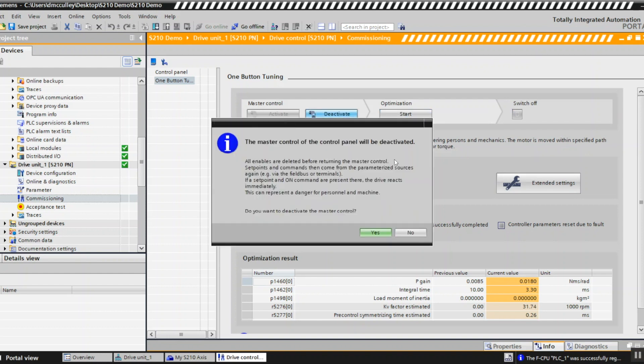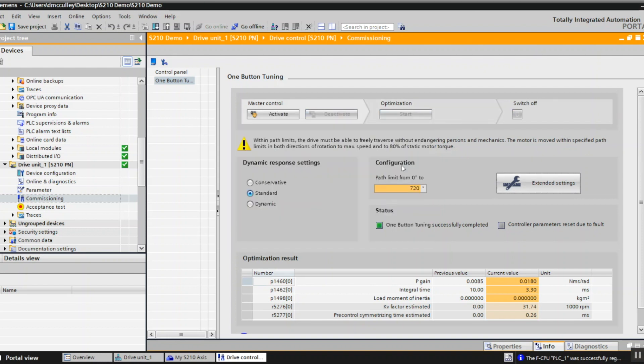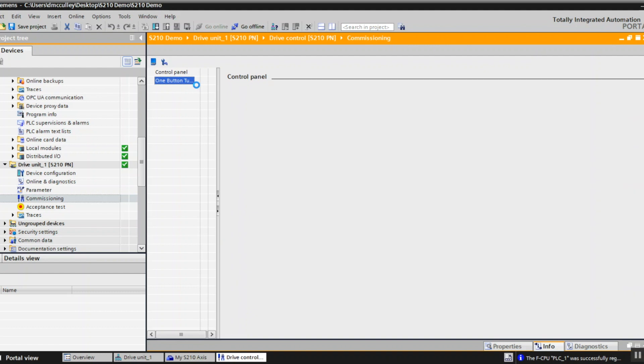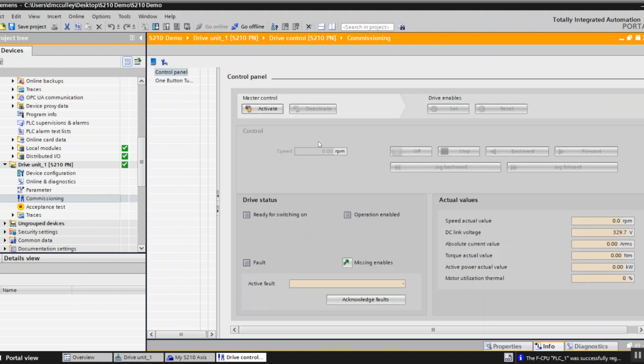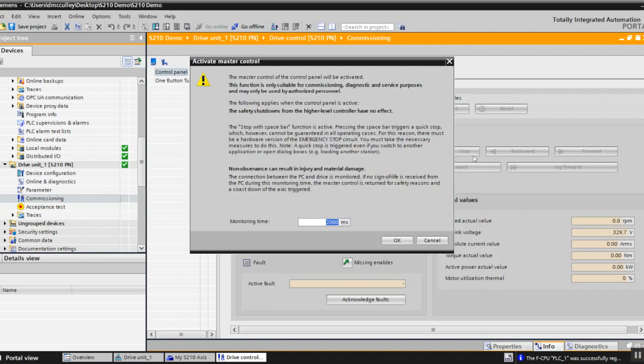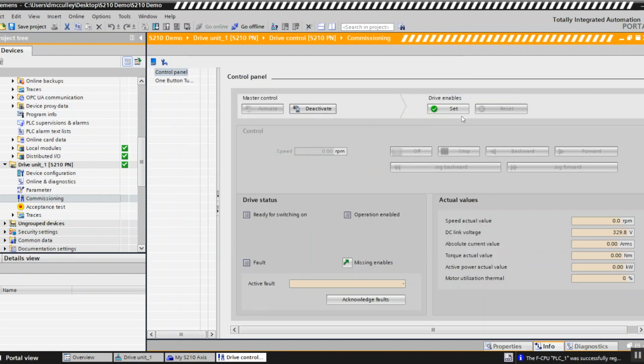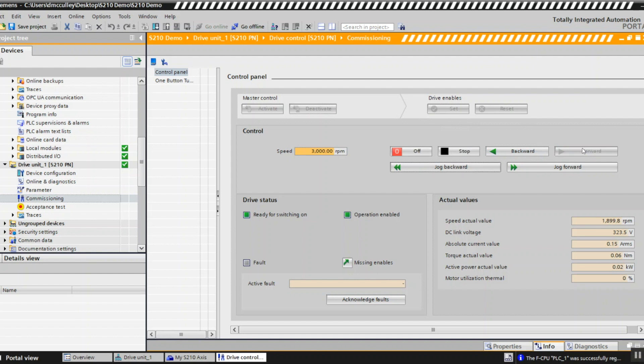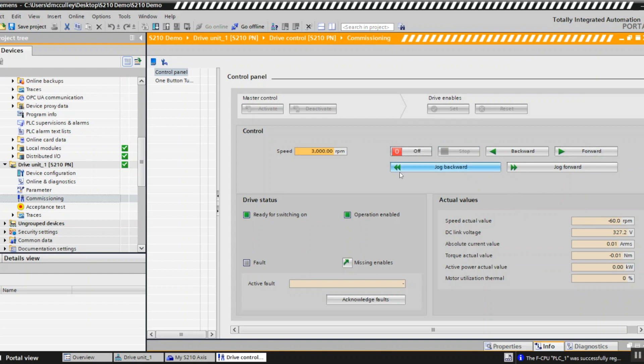I will deactivate that. I can go to my control panel, activate my control panel and put in a speed and go forward. You see I'm running at 3000 rpm. Stop it, backwards, minus 3000 rpm, stop, turn it off. Now my drive is tested.